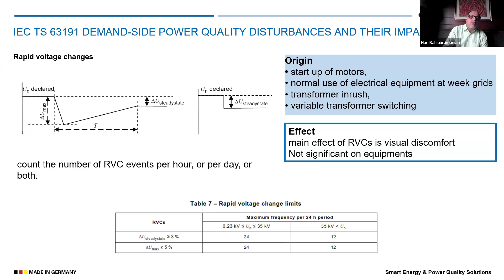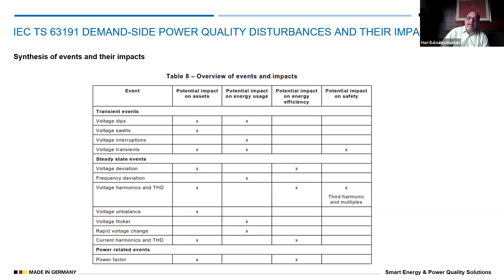Now, this table gives us the potential impacts on the assets and or the energy usage, and how it happens. Say the voltage dips can impact the assets or the equipment. The voltage dips can affect the energy usage of the equipment, and voltage interruptions also impact energy usage. This table is already given, which is very handy when we have to go and explain this to some industries. It also says third harmonics and multiples, or triple N harmonics, are much worse for the safety of the industry itself.